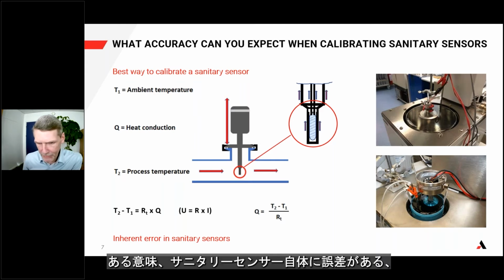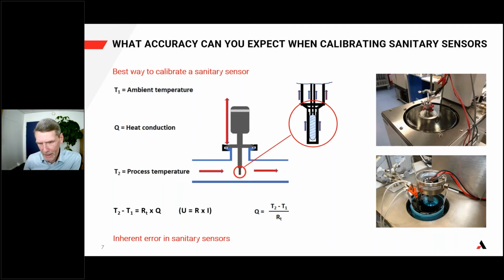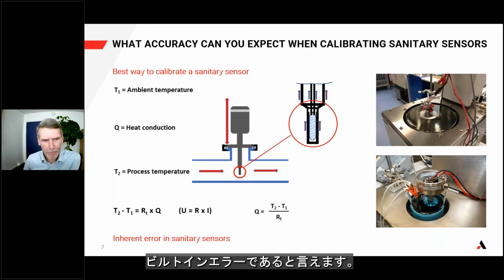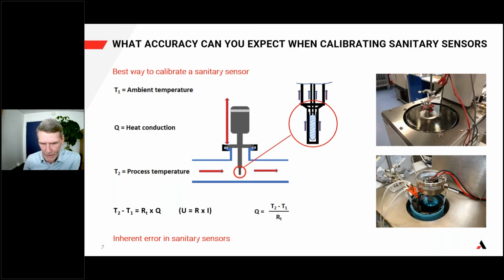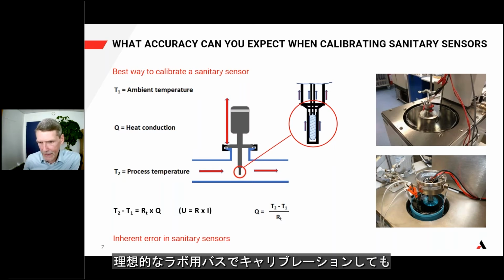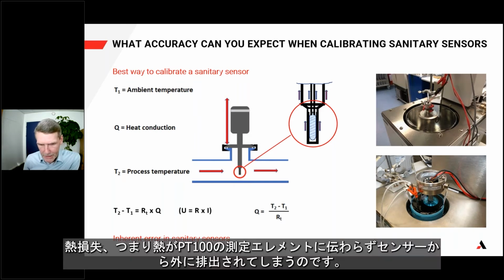In a way, you could say that the sanitary sensor itself has an inherent error, a built-in error. That again means that even if calibrating in an ideal laboratory bath, there will still be an error due to the sensor itself. The heat will go out of the sensor instead of going into the measuring element, the PT100.